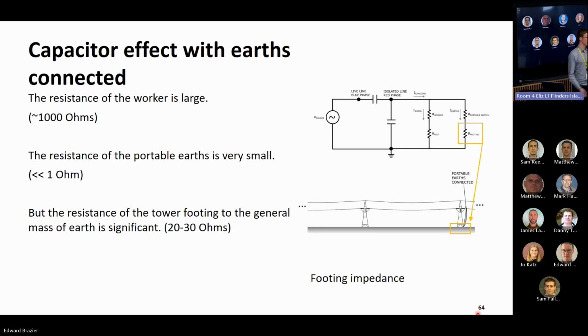Our portable earths, far off in the distance, are connected from the circuit conductors down to the foot of one of the transmission towers. The transmission tower is earthed to the general mass of Earth through some conductors under the ground, and that earthing has an impedance. The tower footing impedance might be 20 or 30 ohms, whereas the impedance of the portable earths will be much, much less than 1 ohm.